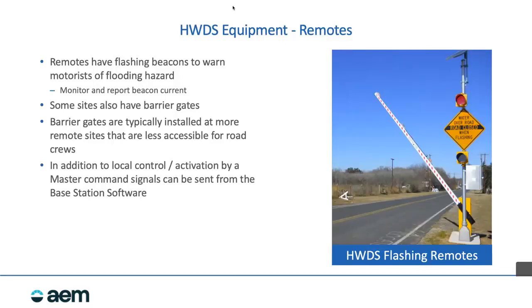I think I missed the very beginning of your question, but I believe it was: can you use an existing stream gauge to be a master? Is that correct? Yes, it would need our controller at the master, but it would be easy to install one of our controllers at a master gauging station and use an existing sensor hooked up to it to send the commands. This would require one of our transmitters and controllers that have this communication capability. As far as the infrastructure, the sensor, all of that would be usable.